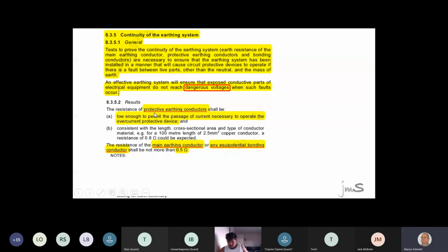The next test is called the protective earthing conductor. Where is the protective earthing conductor? Is that the green wire which goes from the earth electrode to the earth bar, or is it inside the cable? It's inside the cable. Right. When there's an earth in a cable with phase and neutral, we call it a protective earthing conductor. Happy with that? Yeah. How low must that resistance be? Same? No. Read what's coming up there under A. Low enough to operate the protection device.